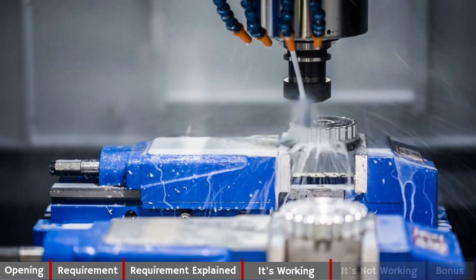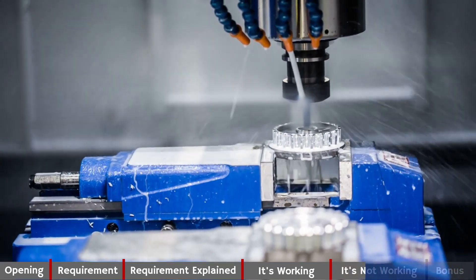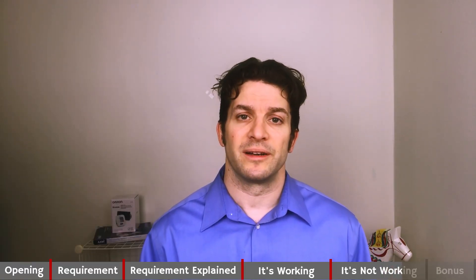So how do I know this is not working? Well first, I've had a recall because manufacturing materials have been left on my product. Second, the processes for removing manufacturing materials aren't documented or aren't validated.